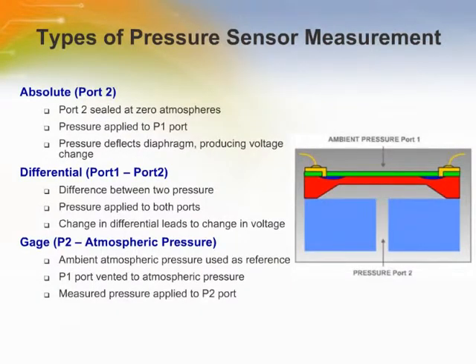HSC and SSC series sensors measure absolute, differential, and gauge pressure. The absolute versions have an internal vacuum reference and an output value proportional to absolute pressure. Differential versions allow application of pressure to either side of the sensing diaphragm. Gauge and compound versions are referenced to atmospheric pressure and provide an output proportional to pressure variations from atmosphere. Note that the output type defines which protocol the sensor uses to communicate.